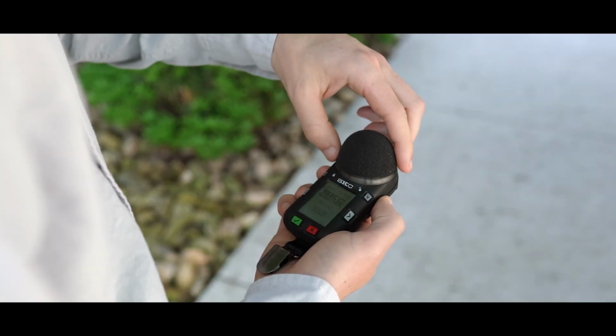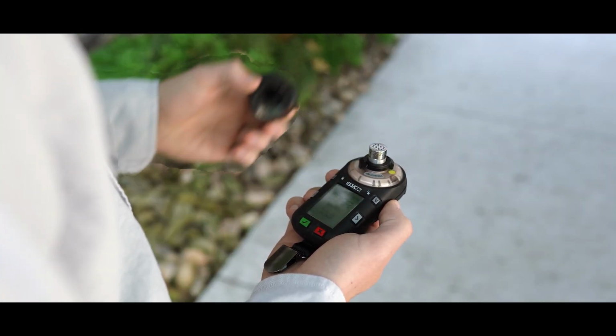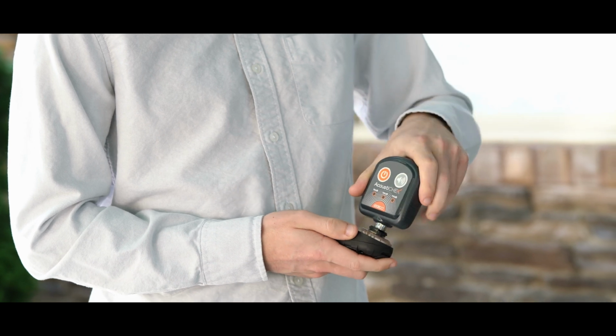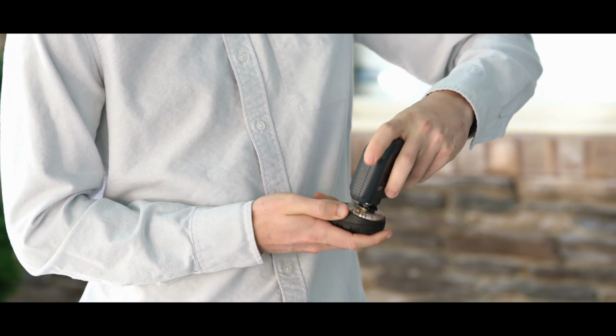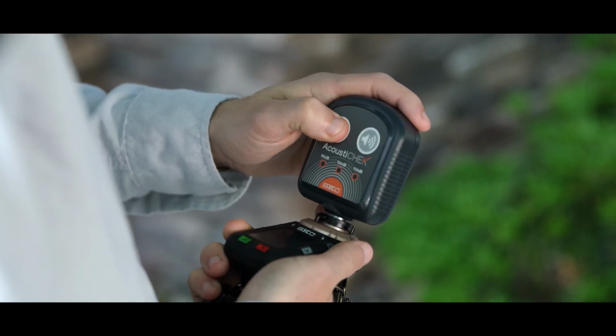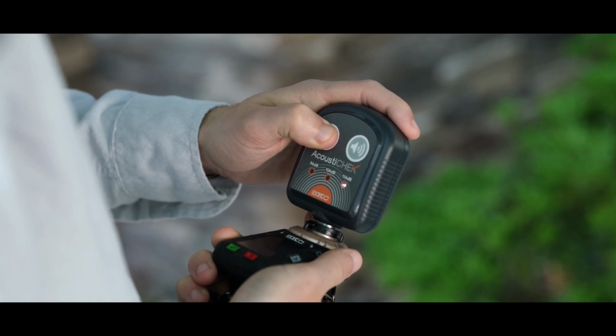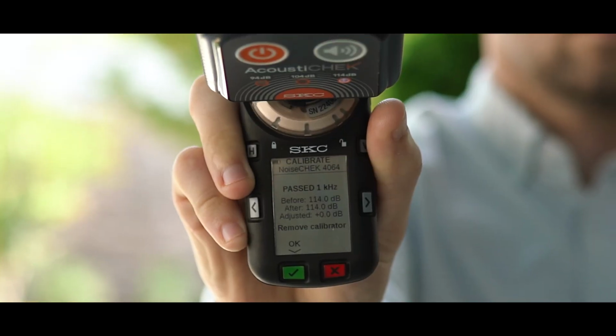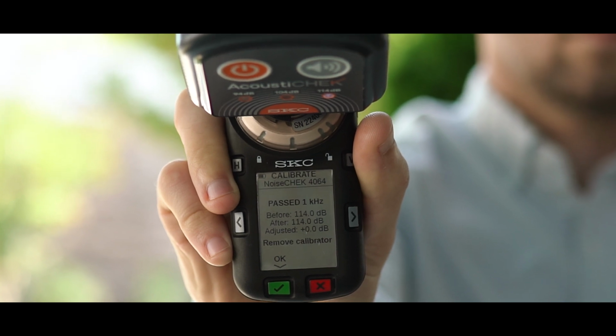So in the development of the NoiseCHEK, we worked with our engineers to develop a system where from the time they introduce the calibrator to the microphone, it automatically goes into the calibration system, and within 5 to 10 seconds, the calibration is complete, showing right on the screen whether you've passed or failed.